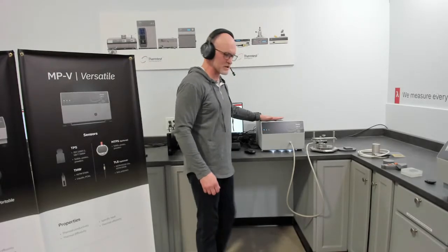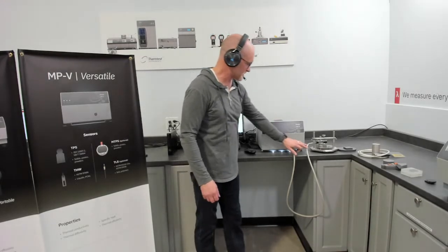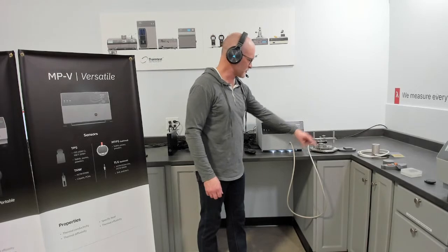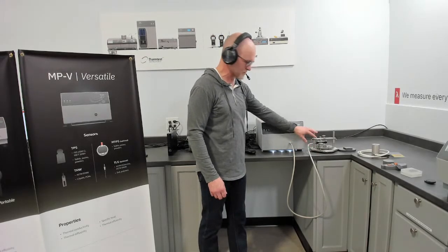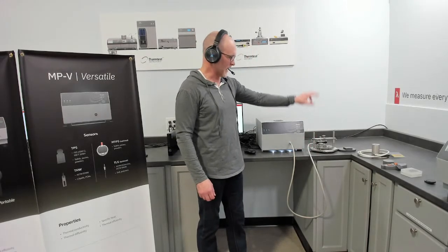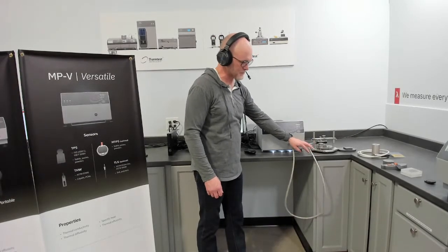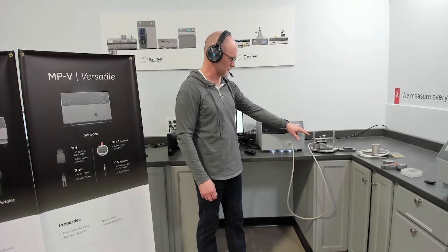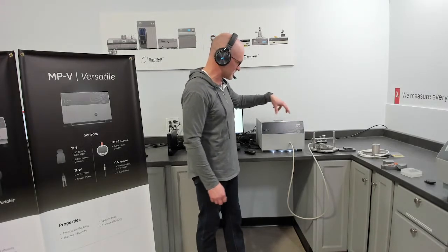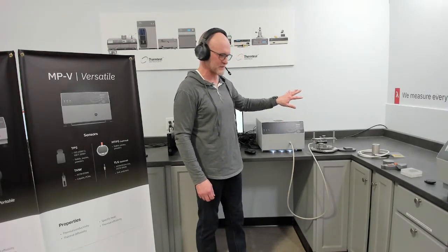These sensors can go up to 300 degrees; it's just the adapter and cable that limits that. The included sample holder and adapters go up to 80 degrees Celsius, which can be upgraded with an upgrade in the adapter up to 300 degrees Celsius. On the low side, all of our sensors and adapters can go to minus 75 Celsius.